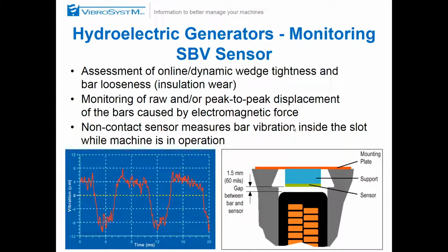For the SBV sensors, you have a sensor here. Well, in fact, the sensor is here. This is a support, because we need to get it close enough to the bar. The sensor is actually mounted on a plate here, and the ripple springs and the wedges are removed here, and our sensor is able to measure the gap from the sensor to the insulation, and we're able to monitor how much vibration occurs at that location on that bar.